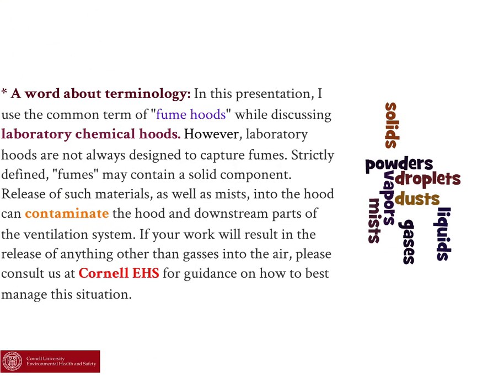A word about terminology. In this presentation, I use the common term 'fume hoods' while discussing laboratory chemical hoods. However, laboratory hoods are not always designed to capture fumes. Strictly defined, fumes may contain a solid component. Release of such materials, as well as mists into the hood, can contaminate the hood and downstream parts of the ventilation system. If your work will result in the release of anything other than gases into the air, please consult us at Cornell EHS for guidance on how best to manage the situation.